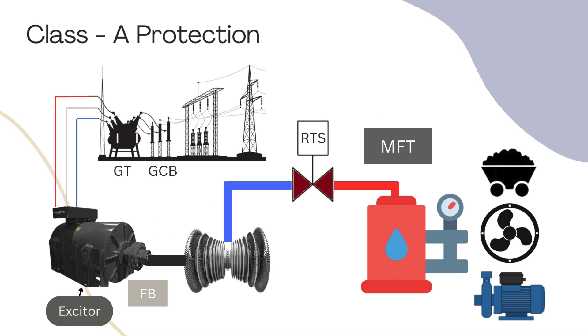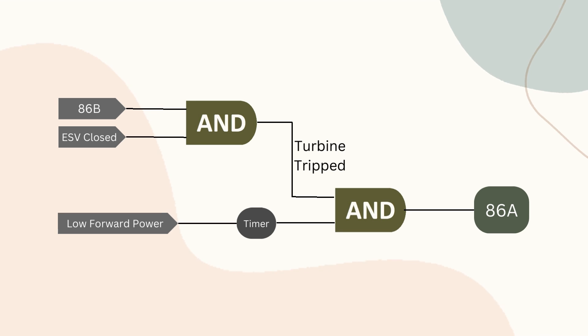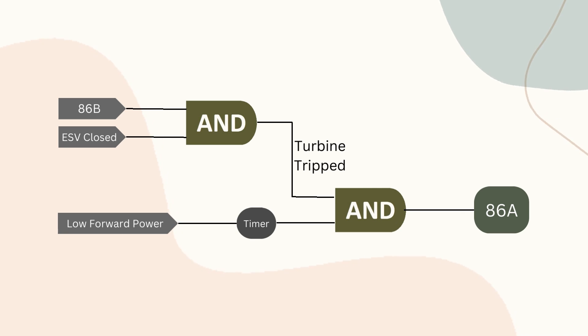When the turbine is tripped, the rotor speed of the generator starts decreasing and cannot send sufficient power, but reverse power flow may happen. Class A protection will operate through low forward power protection. The logic works as follows: the 86B operated and ESV closed signals ensure the turbine is tripped. When the low forward power relay operates after a time delay, these two signals send a command to the 86A relay to trip.